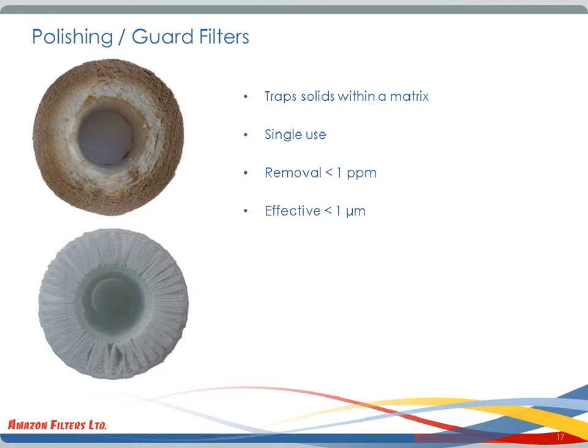They are very efficient and can remove solids that cannot be removed by other methods, and they are also the piece of process equipment least sensitive to upset conditions. That is, if something changes upstream in the process, then they will still meet their removal efficiency requirements. This is why they're very useful as a final stage, hence known as guard filters, because if upstream equipment fails or the process changes, then downstream equipment or disposal environmental requirements will not be breached.